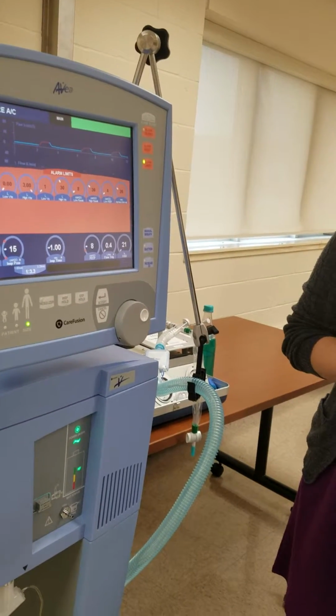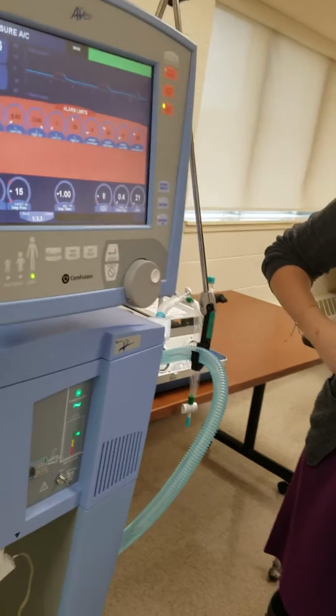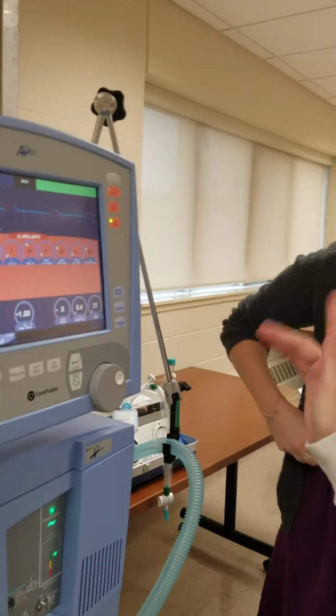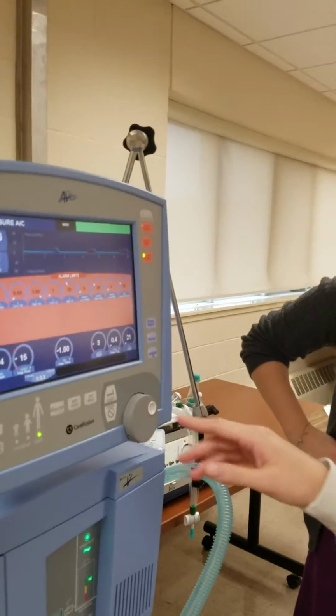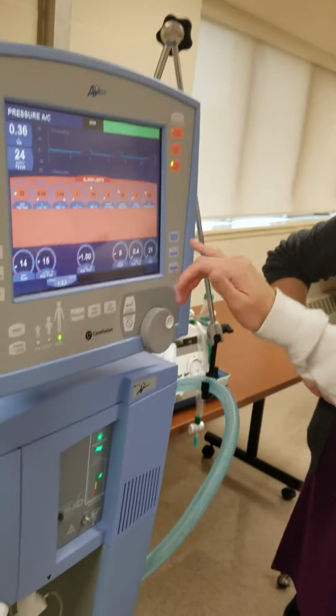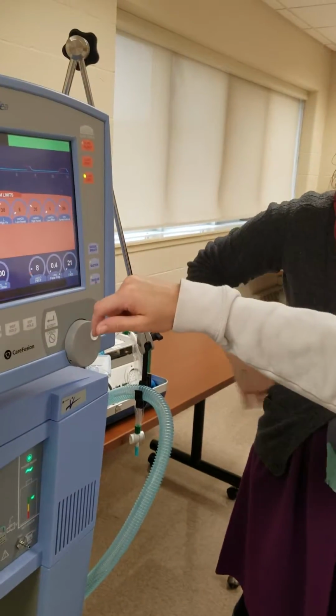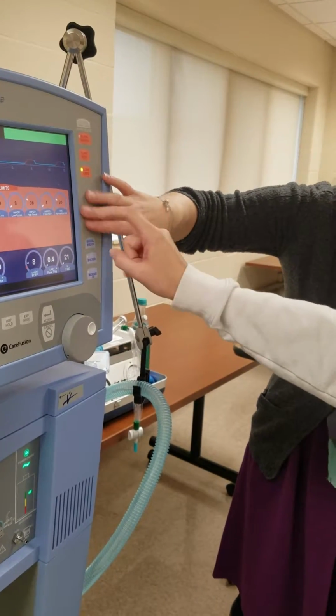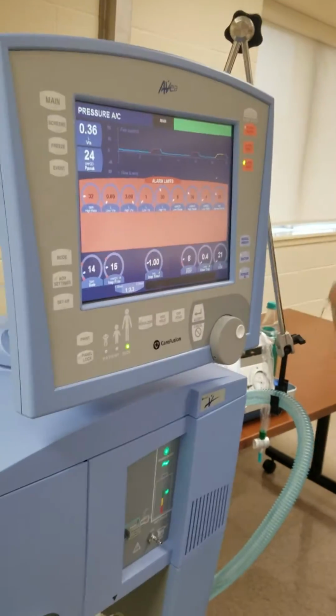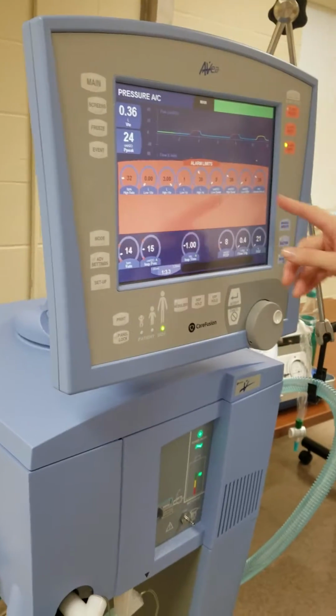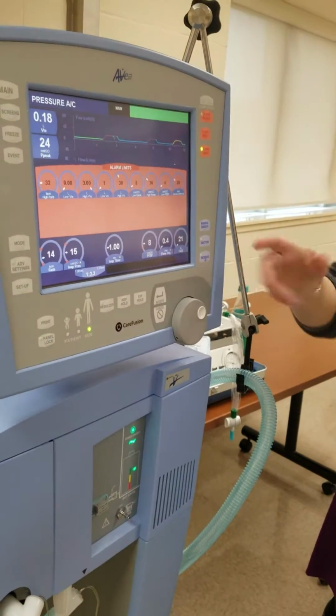Do you want to do the alarm limits then too? So with like the V60, is it kind of like the same to where you'd want like, I know we didn't touch something that was 20. Yep, so apnea interval pretty much is always 20. If they've gone 20 seconds without taking a breath, we should probably take another breath. And then for PEEP, we usually do about 2 below.